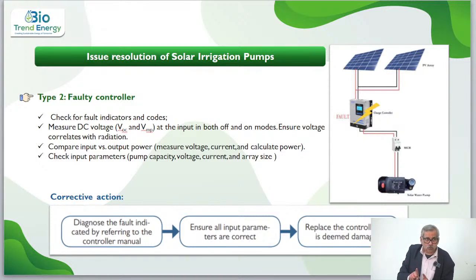As I told you, always remember voltage is directly linked to the radiation. If my radiation is low, my voltage also will be low. If my radiation is good on that day, output voltage has to be of that level. Then compare input and output power, measure voltage, current, and calculate power. Check input parameters: pump capacity, voltage, current, and array size.